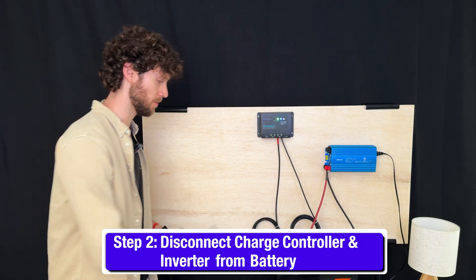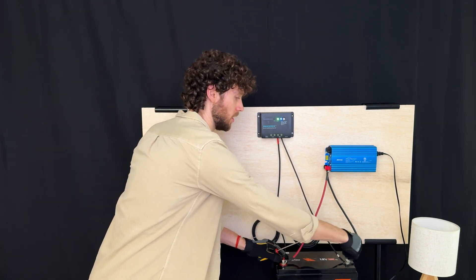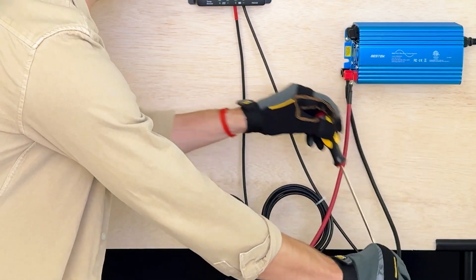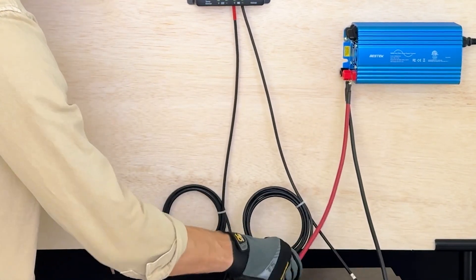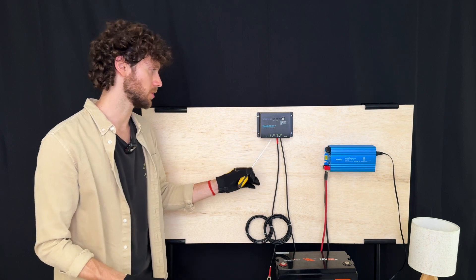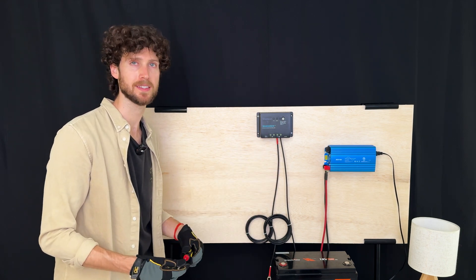The next step is to disconnect everything from your battery. So I'm going to remove these caps and use my screwdriver to unscrew the bolts. And obviously once that's done, the charge controller and the inverter will lose power and we can start working on this system.